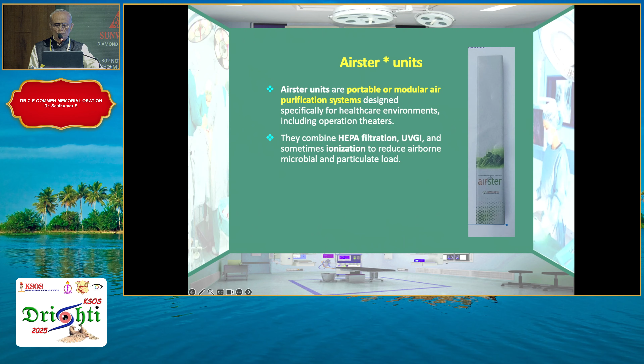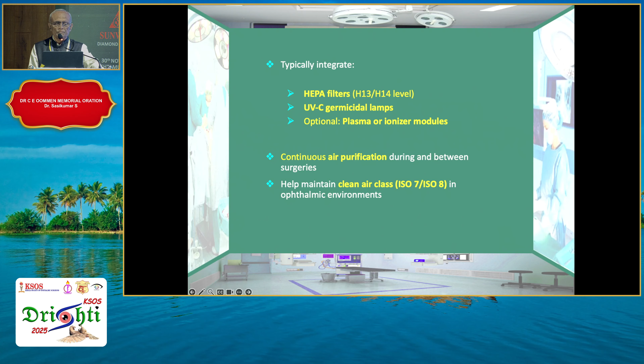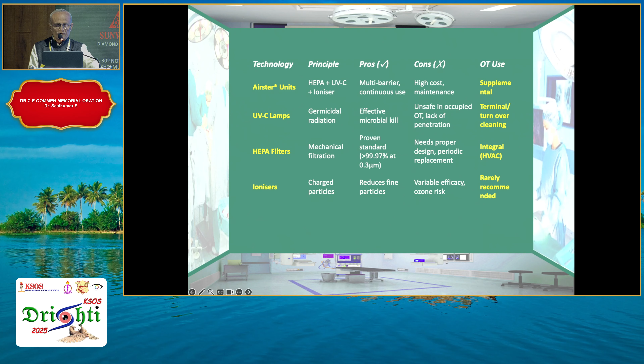Recently, one company has come up with a portable modular air purification system incorporating HEPA, UVGI, and ionizer modules. They claim to provide continuous air purification, giving about class 7 or class 8 purification, but it can only be used as a supplemental device. So to sum up regarding these alternatives, Airster units can only be supplemental. UVC lamps can be used for terminal or turnover cleaning. HEPA filters are an integral part of HVAC systems. Ionizers can be used, but it's rarely recommended.